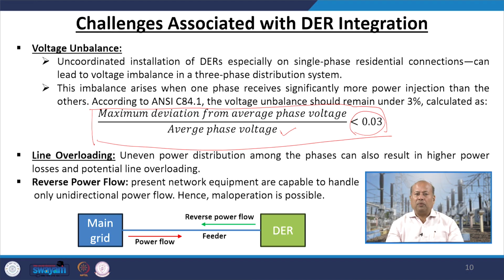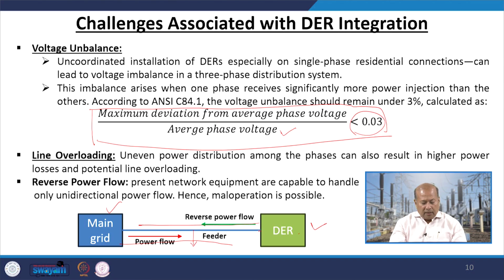Now, what about the reverse power flow? As you all know, the moment you connect a DR to the main grid, previously the power is to come through this way, right, if there is a consumer. But because of DR, there could be a reverse power flow. Am I right? So, the grid to load and the DR to the main grid, the feeder may now carry power in a reverse direction compared to the previous case where the load is being catered from the main grid only. Now, there are two different challenges. For example, if I connect a load here, now if the DR source current is too high, which is more than the load requirement, then probably it will start flowing this way.